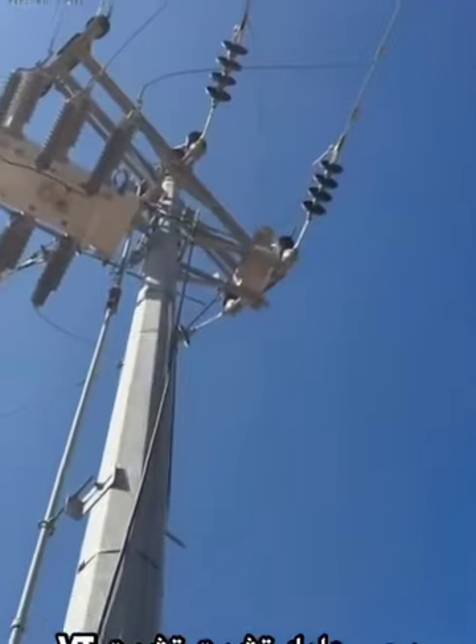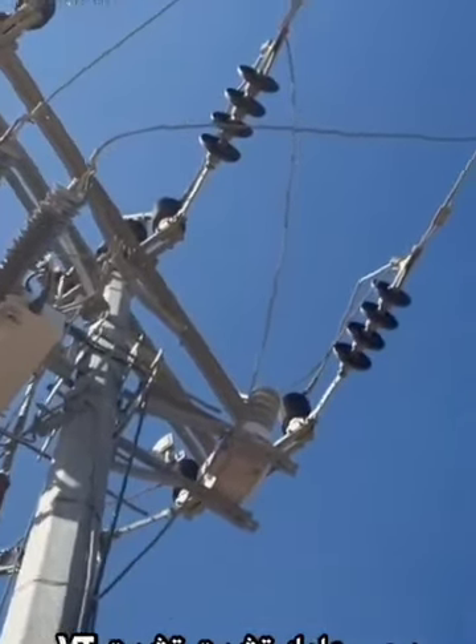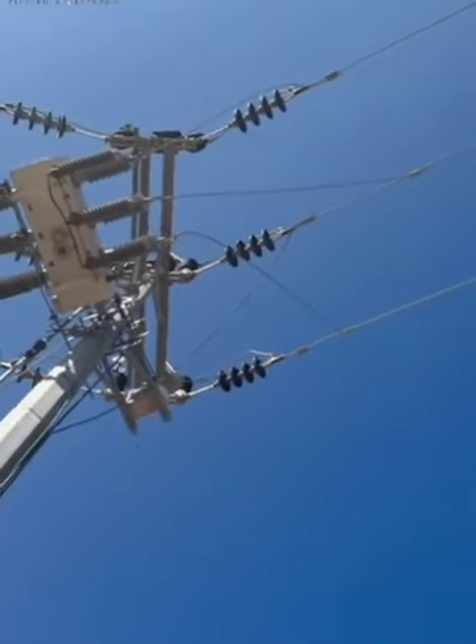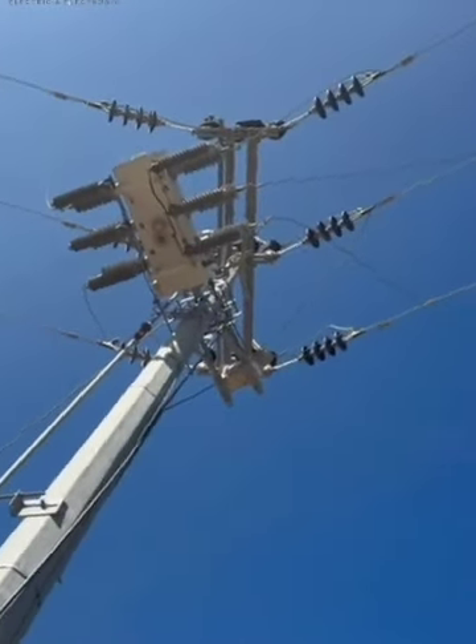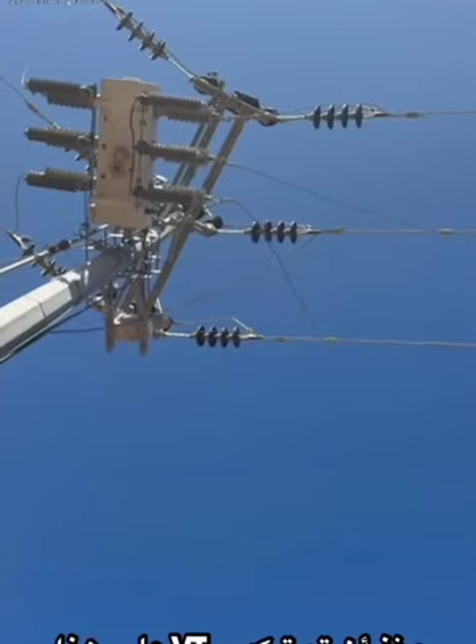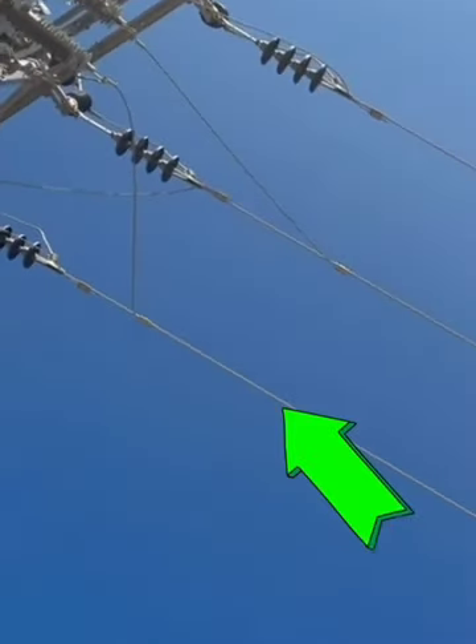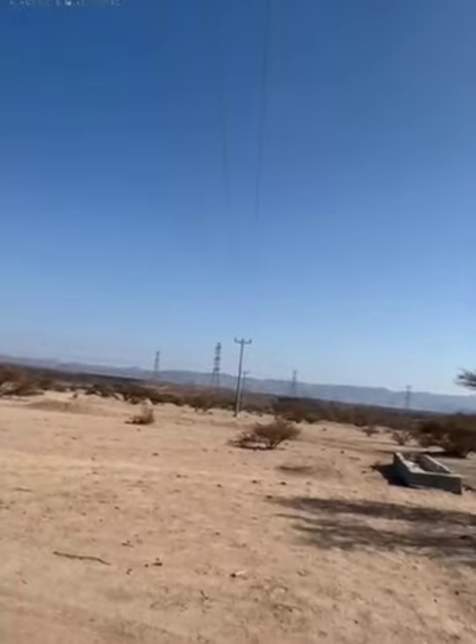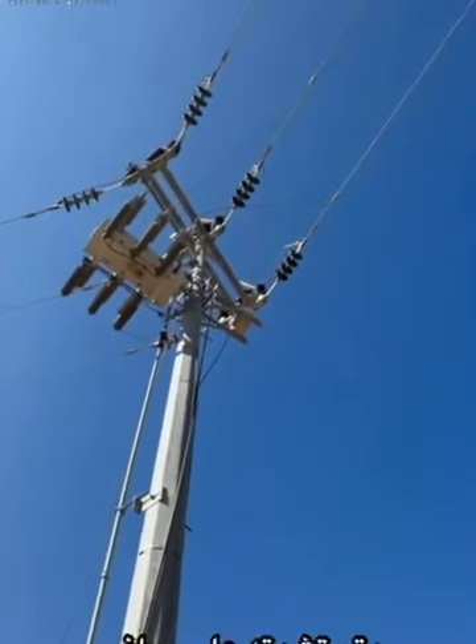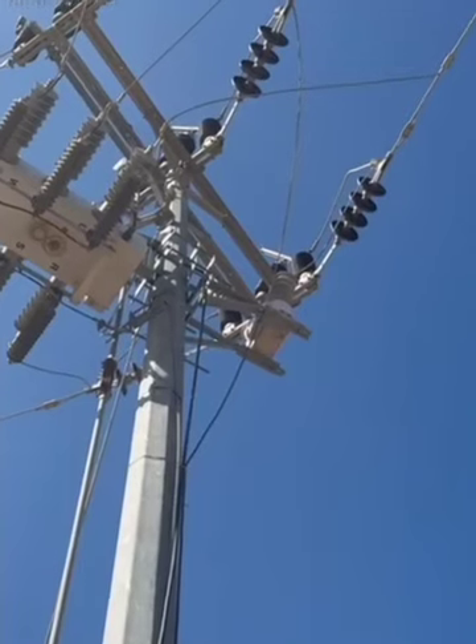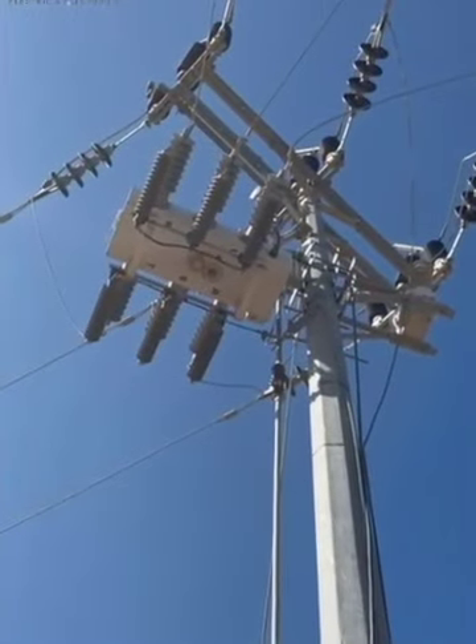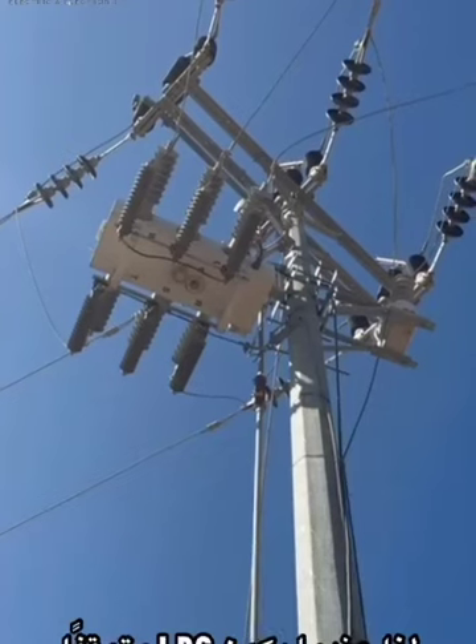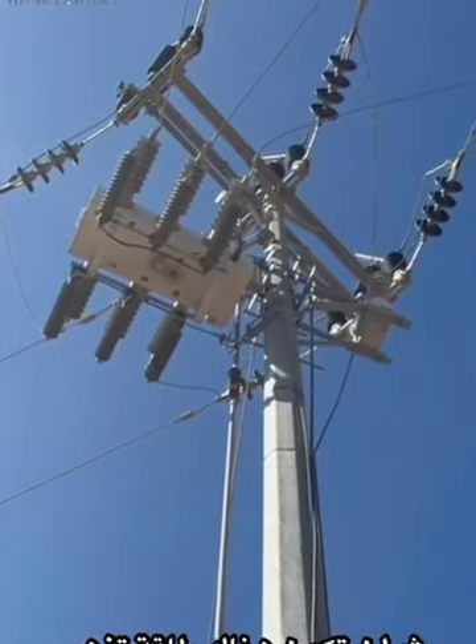And when you install the LBS, you have to install the VT on the source side. Practically in this video, in this site, since the VT is installed on this line, it should be the source side, giving the power. Because if the VT is installed on the load side, then when you open the LBS, so when the LBS is off, there will be no power going to the controller.